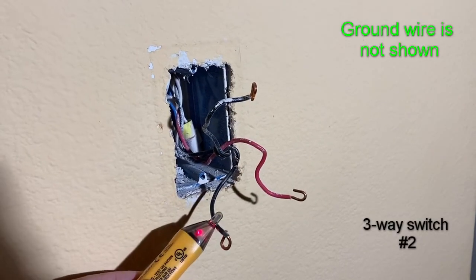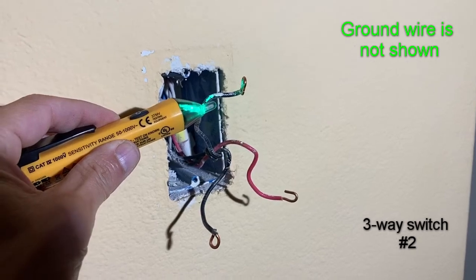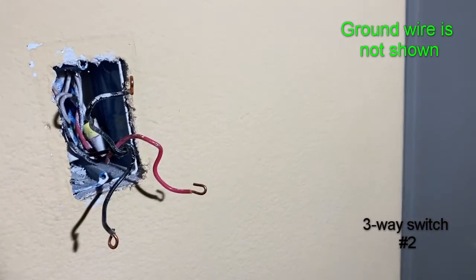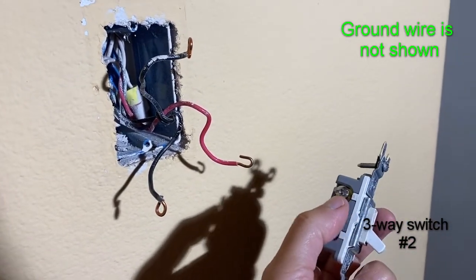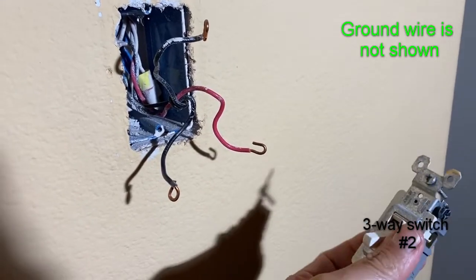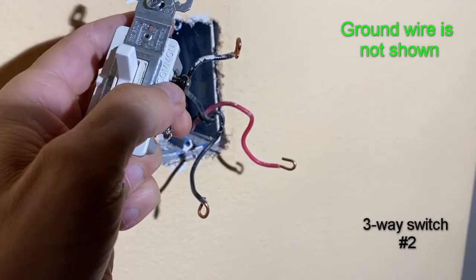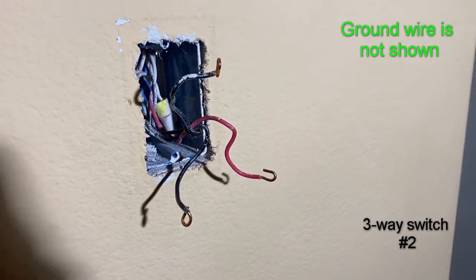Let's test and see which one of these two black wires is hot — that's the wire that connects to our common side. Well, it's not this one. So there it is right there — that's going to be our common connection. These two are travelers; they can connect to either of the two terminals on the main body. The identified black wire connects to our common terminal, which has the black screw.